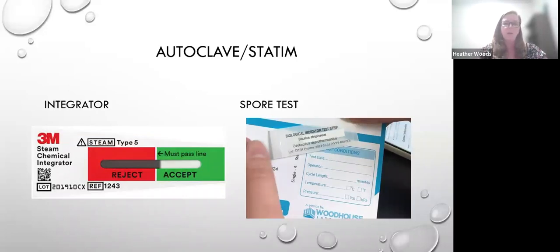And then on the right, we have our spore testing. The spore testing assesses the killing of Geobacillus spores, which are highly resistant to heat and typically used as a biological indicator for sterilization. It's important that these are used together when trying to achieve sterilization, because the integrator identifies that sterilization was achieved during each cycle. The spore test verifies, with a weekly recommendation, that there's no pathogenic contamination.